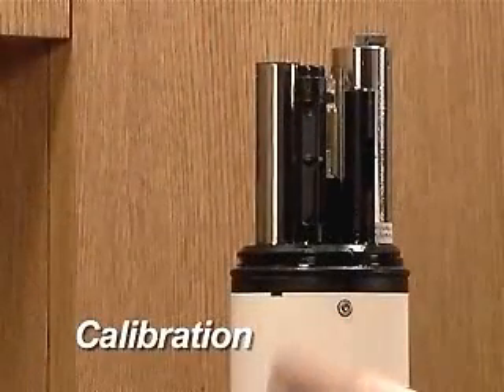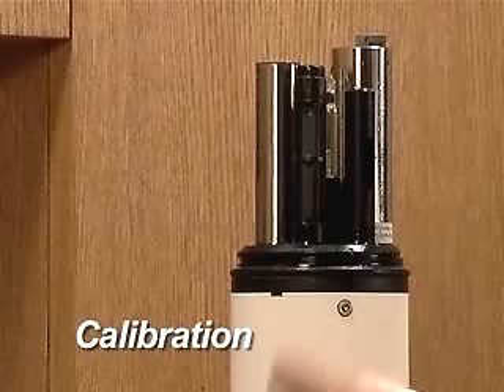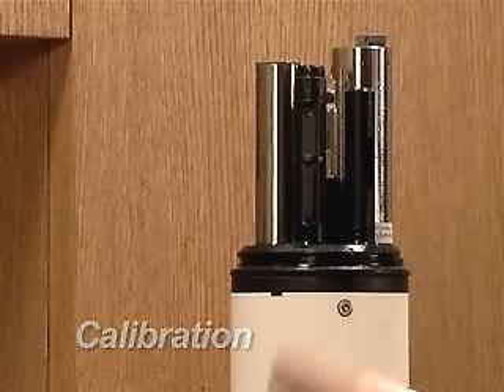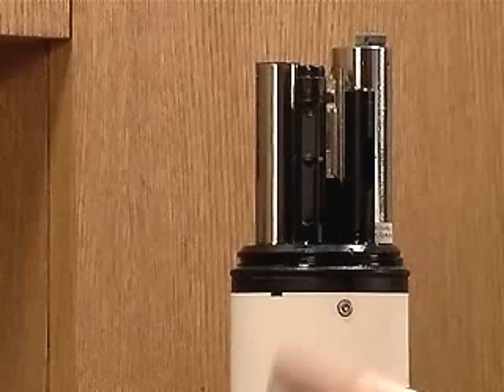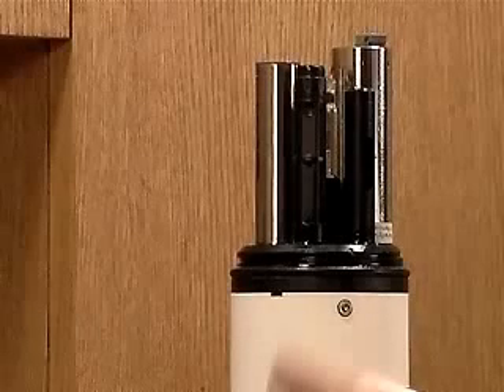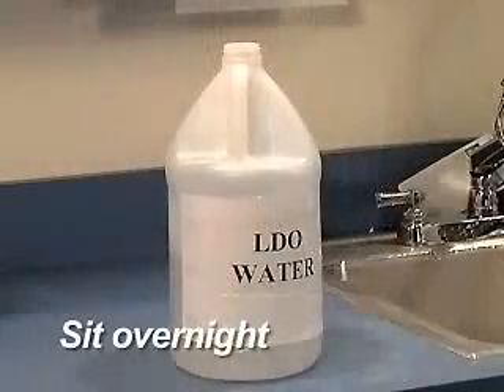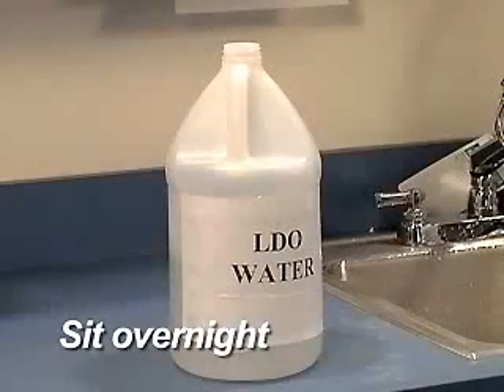Calibration. The LDO sensor compensates for the temperature of the water. To perform an accurate calibration, it is important that the temperature of the water remain constant during the procedure. The easiest way to do this is to allow the water used for calibration to sit overnight in an open container until it equilibrates to room temperature.